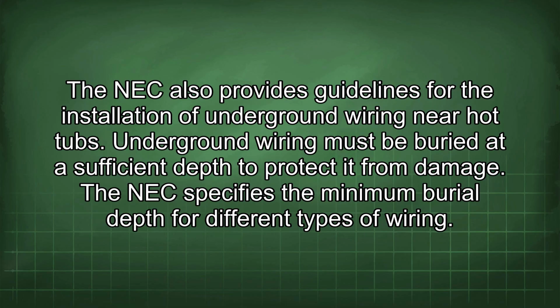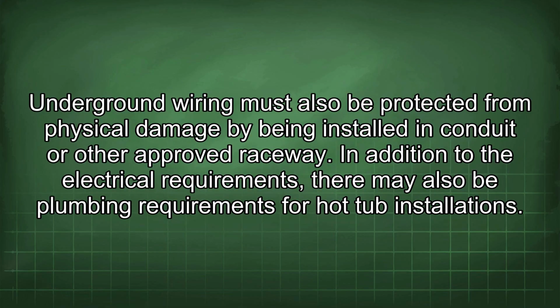The NEC also provides guidelines for the installation of underground wiring near hot tubs. Underground wiring must be buried at a sufficient depth to protect it from damage. The NEC specifies the minimum burial depth for different types of wiring. Underground wiring must also be protected from physical damage by being installed in conduit or other approved raceway.